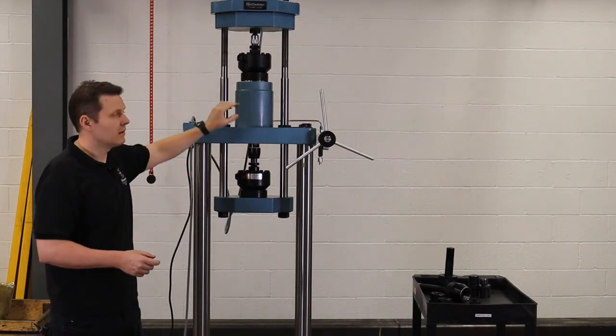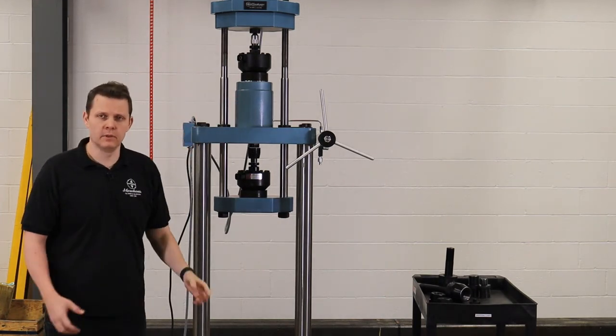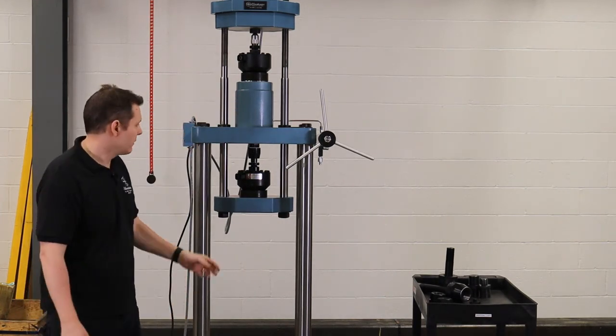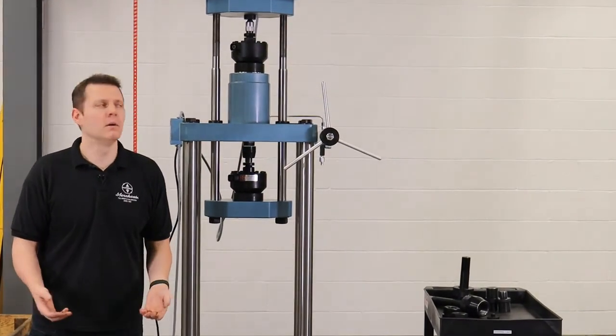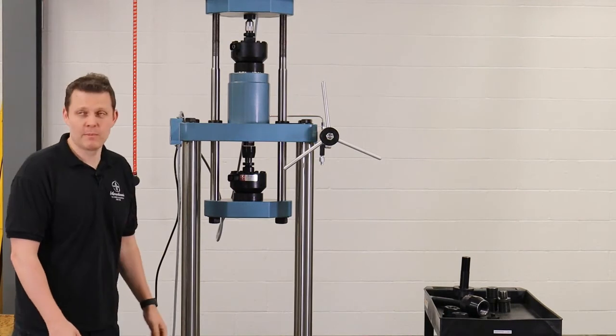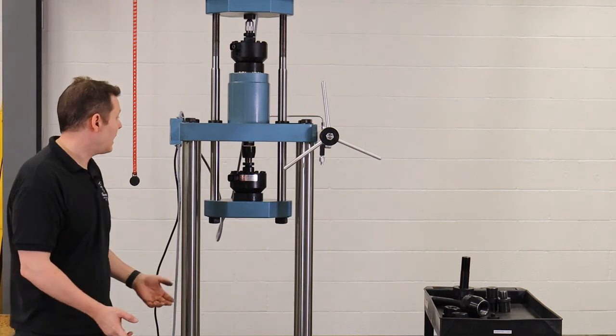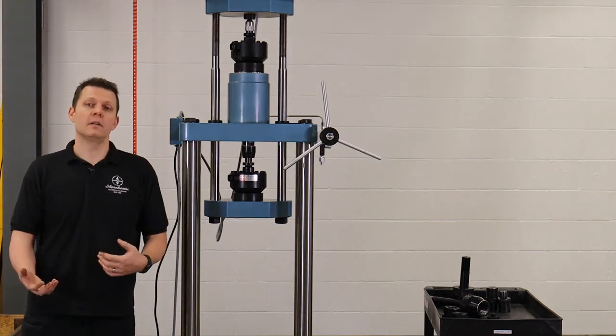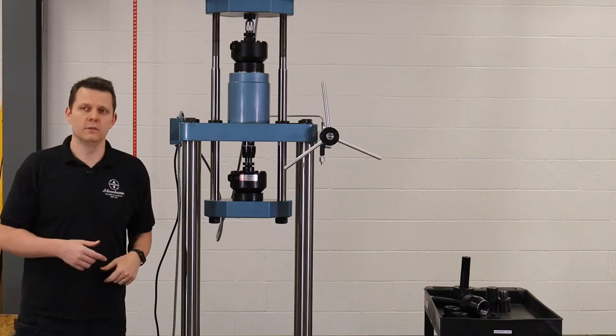Going beyond that could cause some damage, so therefore we get it here. The actual deflection is really low. We're not going to extend that jack by more than a quarter of an inch in this case scenario. And that's what you have there. There you have how you mount a load cell in compression in the Morehouse 100k UCM.